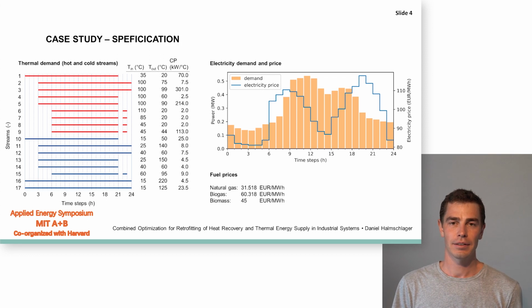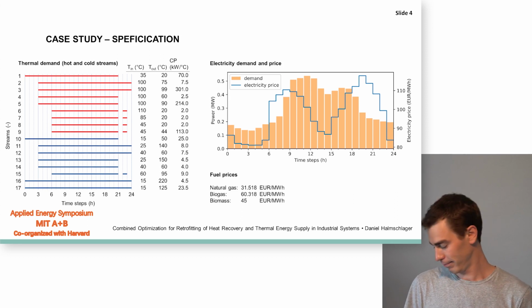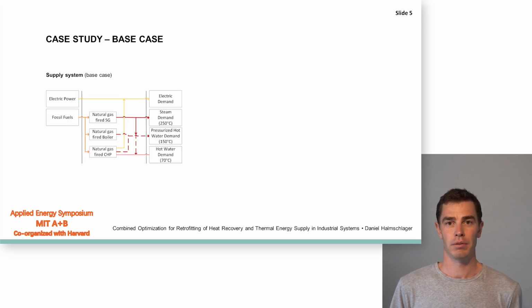Additional input factors are the investment cost for all the equipment, but listing these in detail would be too much for the scope of this presentation. As we are dealing with a retrofit case, we have an existing system where the thermal demand of the process is supplied via 3 temperature levels: steam, pressurized hot water and hot water by a natural gas-fired steam generator, a natural gas-fired water boiler and a natural gas-fired combined heat and power plant. The electric demand is supplied by the CHP plant and through the grid.